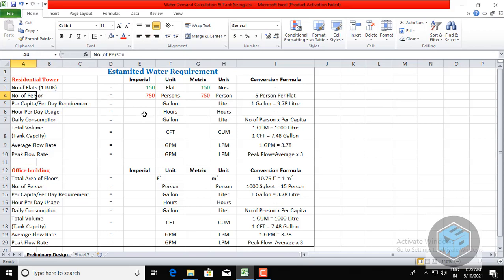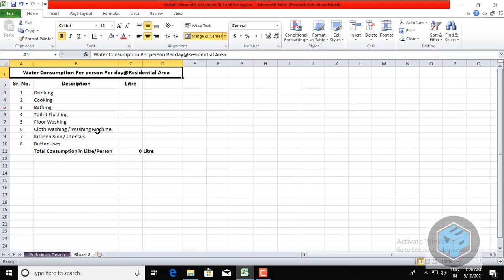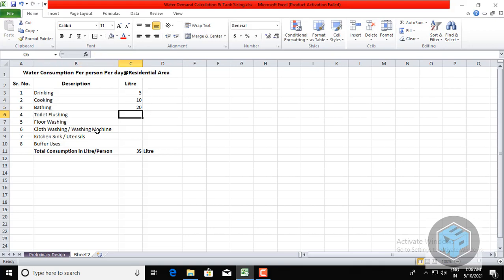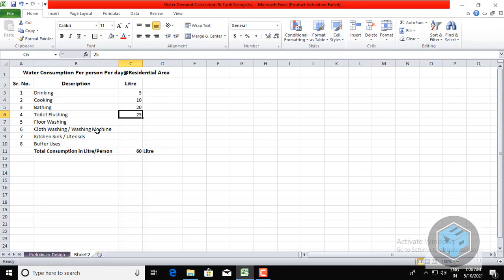The number of persons is 750. Now let's talk about the per capita per day requirement — this is the actual water requirement per person per day. For a single person at a residential area: drinking water is 5 liters, cooking is 10 liters, bathing is 20 liters (one bucket), toilet flushing is 25 liters — the largest single use — and floor washing is 15 liters.